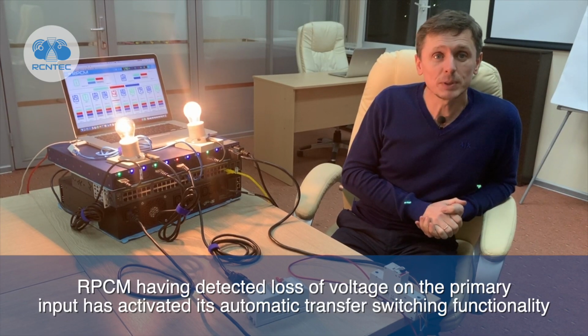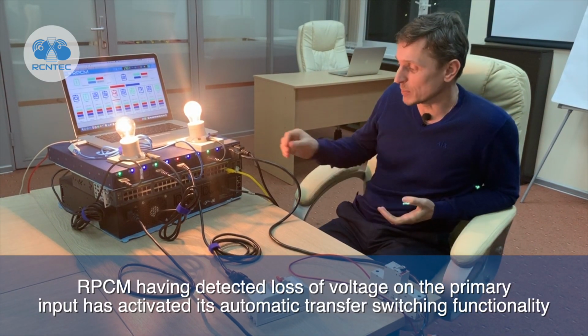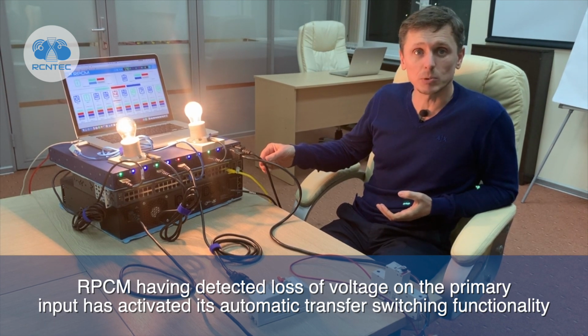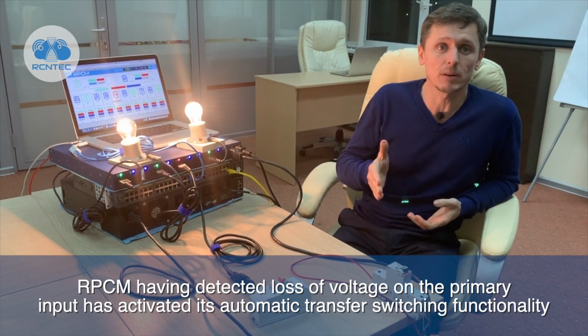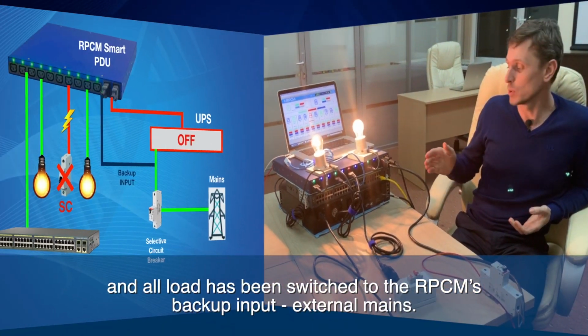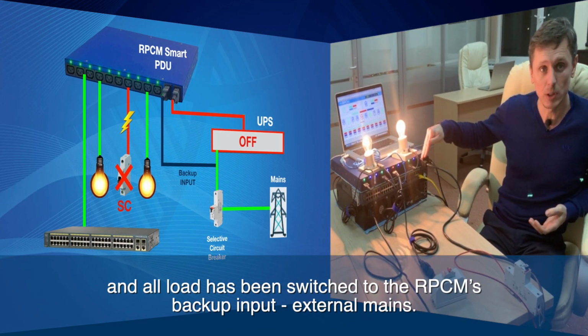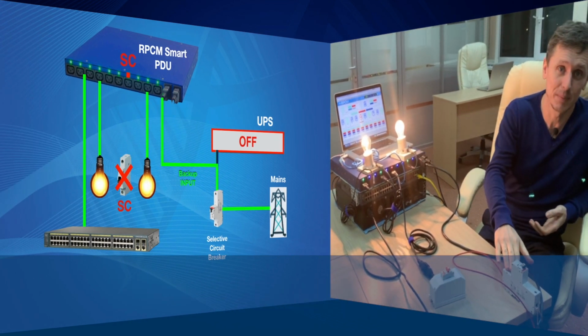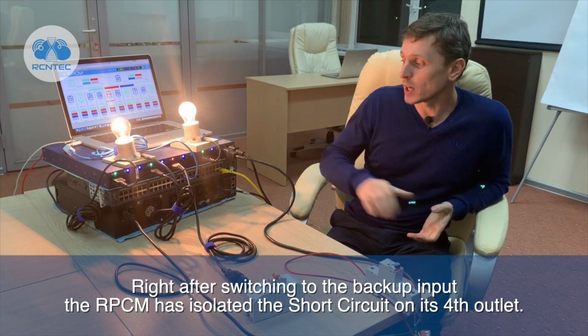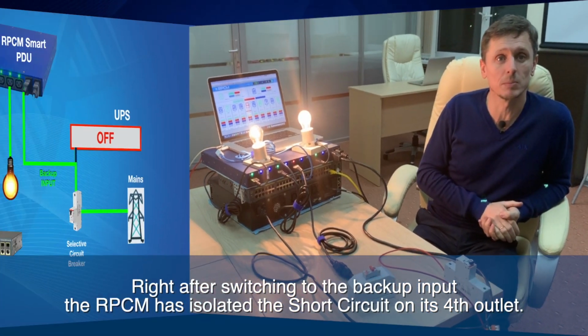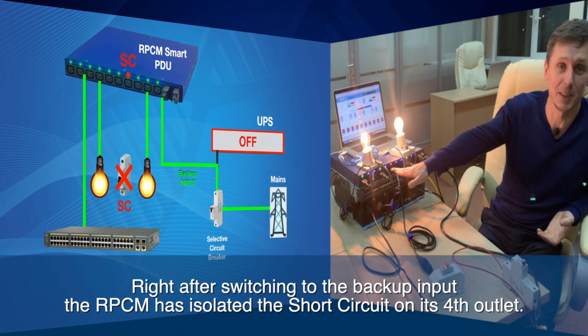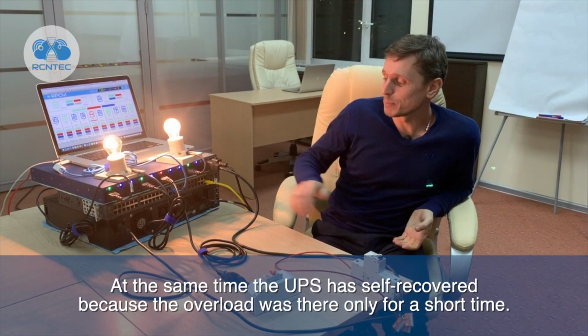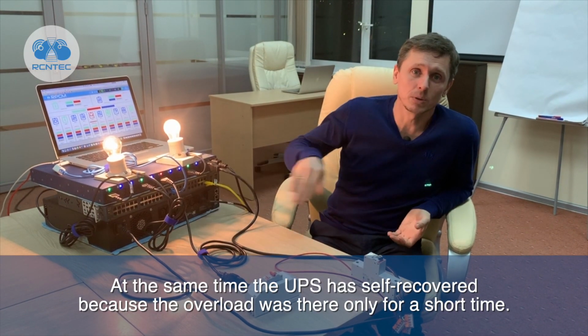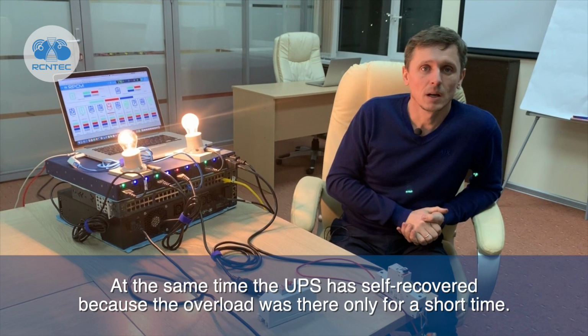time. RPCM, having detected loss of voltage on the primary input, has activated its automatic transfer switching functionality, and all load has been switched to the RPCM's backup input, external mains. Right after switching to the backup input, the RPCM has isolated the short circuit on its fourth outlet. At the same time, the UPS has self-recovered, because the overload was there only for a short time.